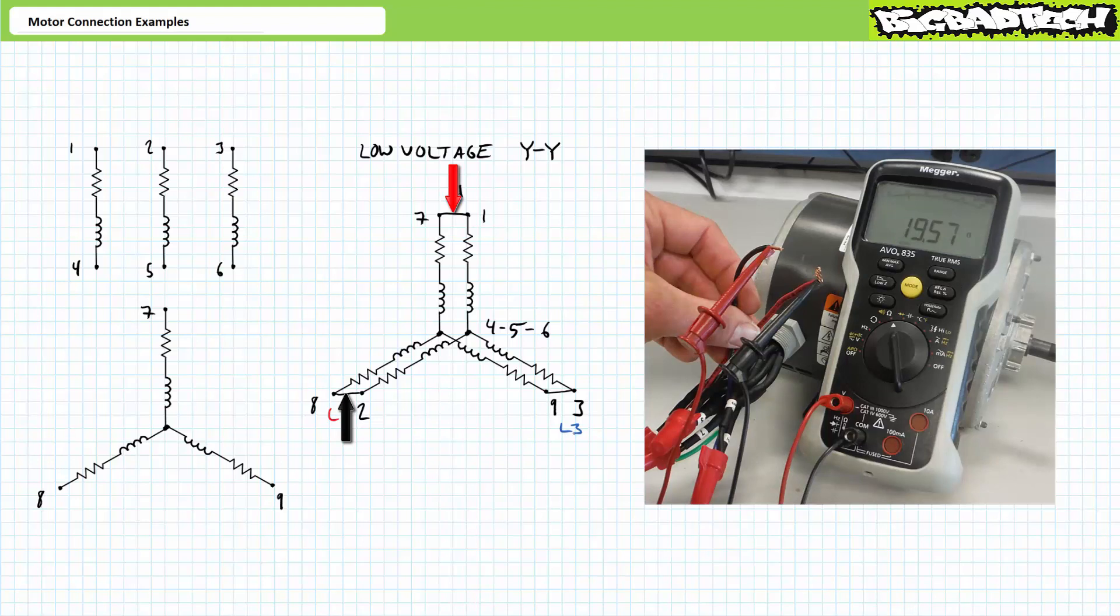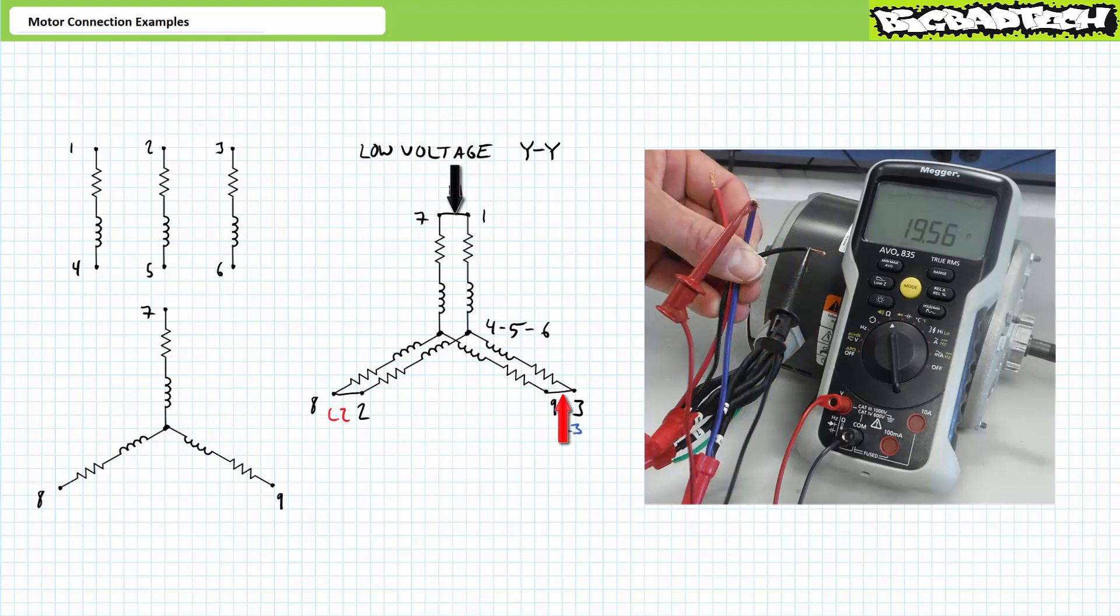The same observations can be made about points two-eight to three-nine and three-nine back to one-seven. An ohmmeter between conjoined terminals two-eight and three-nine does indeed see resistance of roughly 20 ohms as does an ohmmeter between conjoined terminals three-nine and one-seven as we might expect.